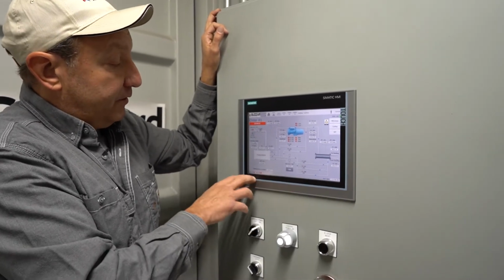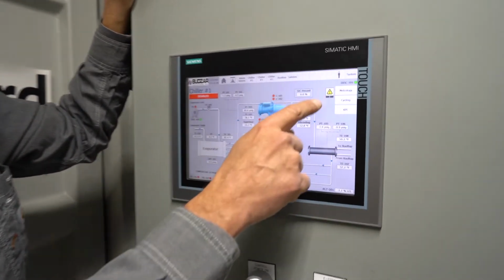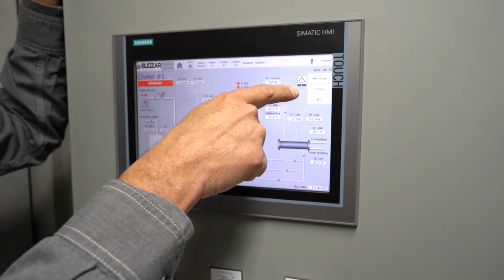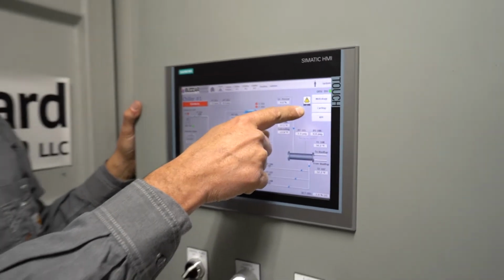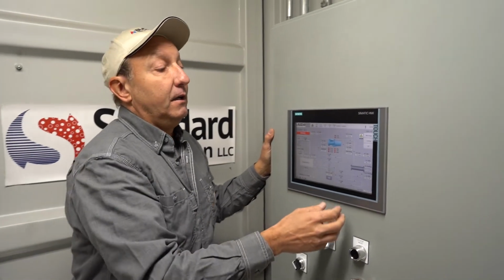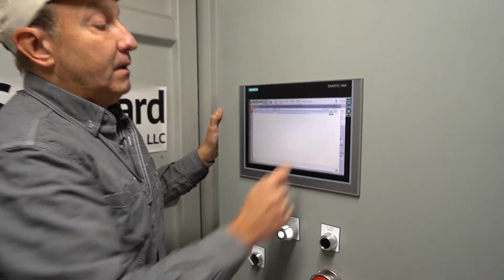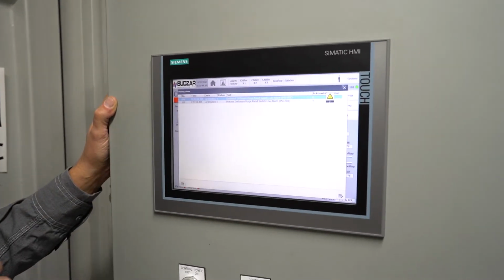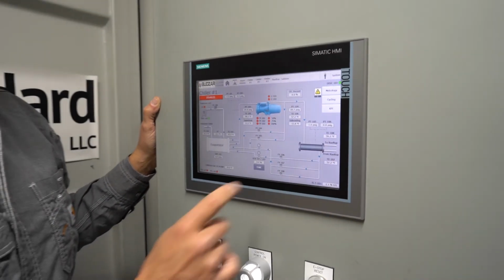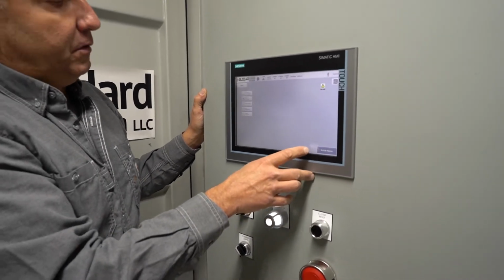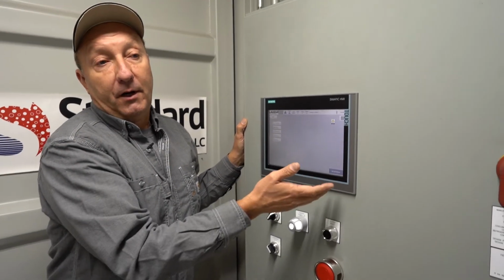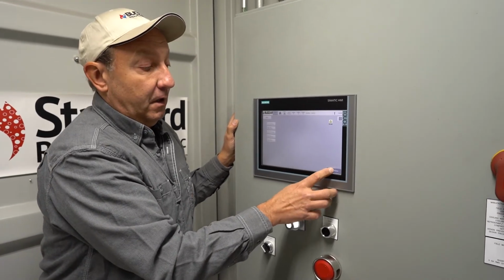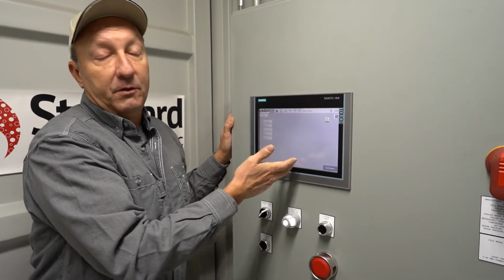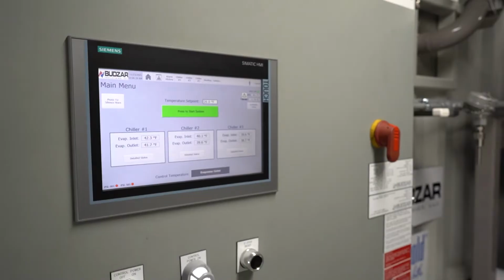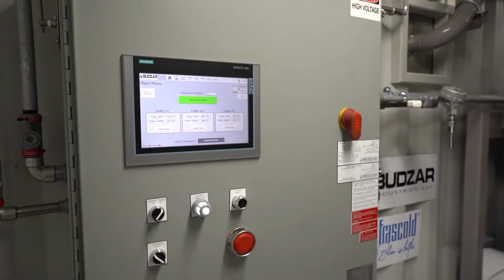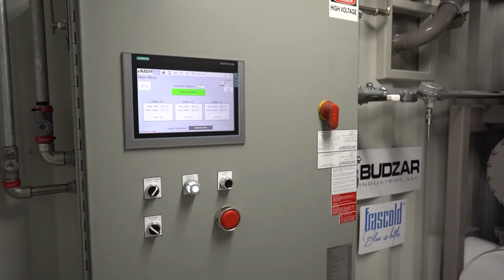We have a lot of information here, and we have our alarm indicator. Right now we have a couple alarms just because our purge systems are not being utilized, again, because we're recording and filming. But if you hit the alarm button, you get your active alarm screen. And we programmed a one-button acknowledge all. So in the event of an alarm, once you address the problem or correct the problem, then you just hit acknowledge all, and the alarms, in the event that they are cleared or the problem is no longer active, the alarm will acknowledge and clear, and you reset basically.